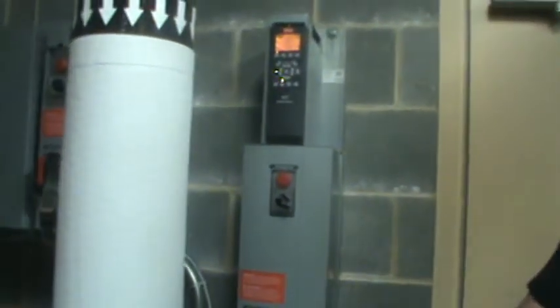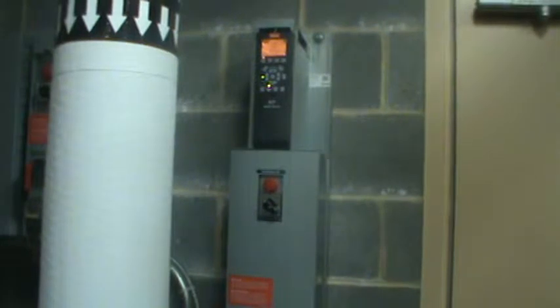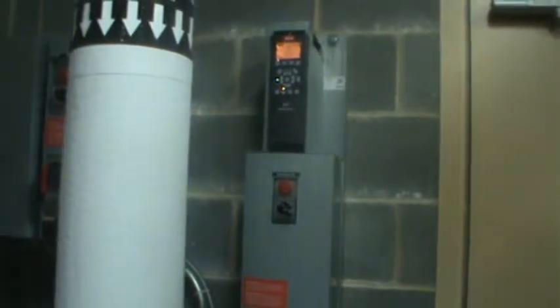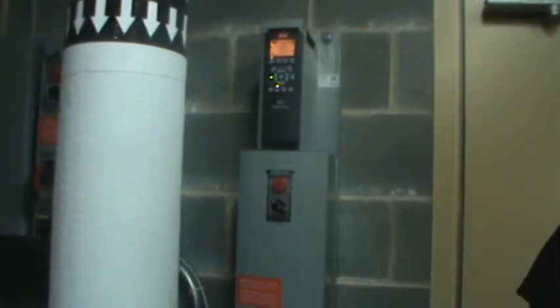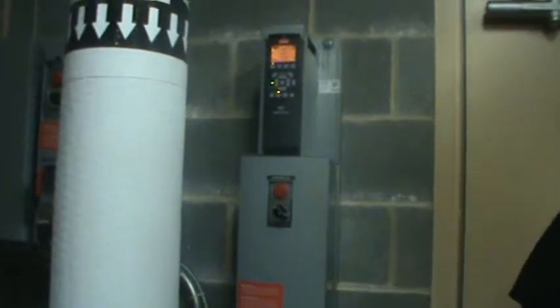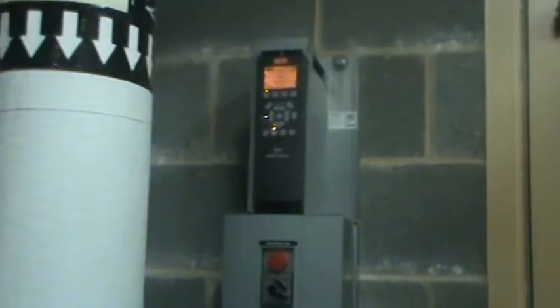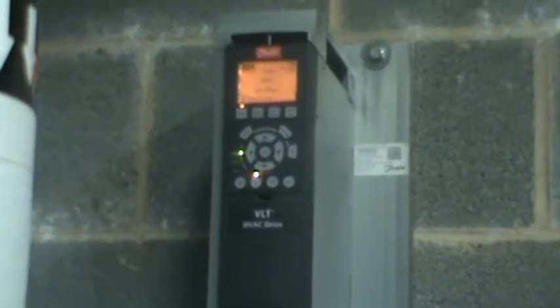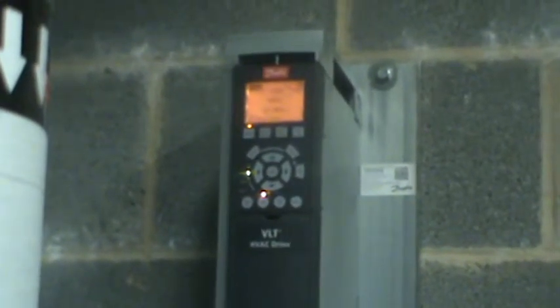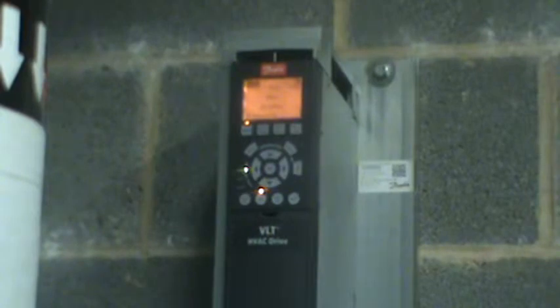All right. Keep the area around them comfortable. You know, not a lot of excess dirt. Definitely no water. And don't pile anything on them. Don't hang anything on them. If you do got to do some work in here and you think it's going to be really dirty, if you can shut them down, awesome, because there is a fan that will just suck all that dirt and stuff through them. You know, if you're running gas, it's not really a problem. But if you have a big boiler prop or something like that, you're creating a lot of dust. If you have the opportunity to shut them down for the most of the work, shut them down, do your job, and fire them. It'll just save some wear and tear on the drives.